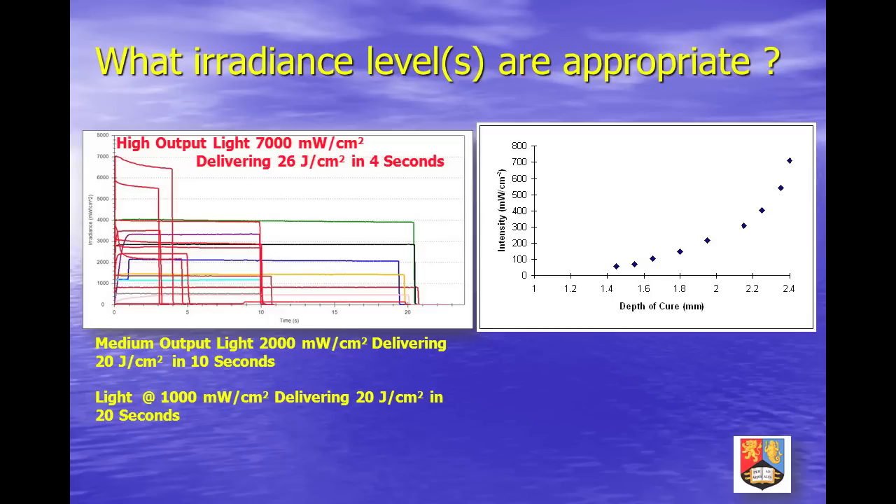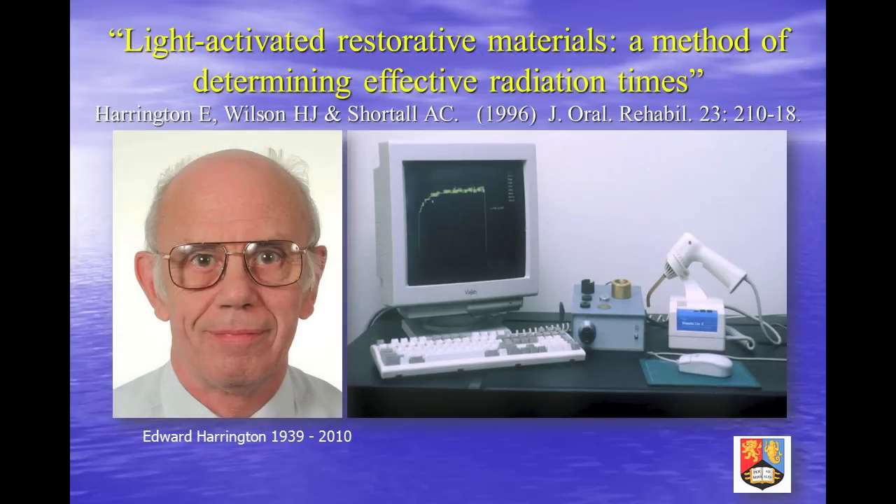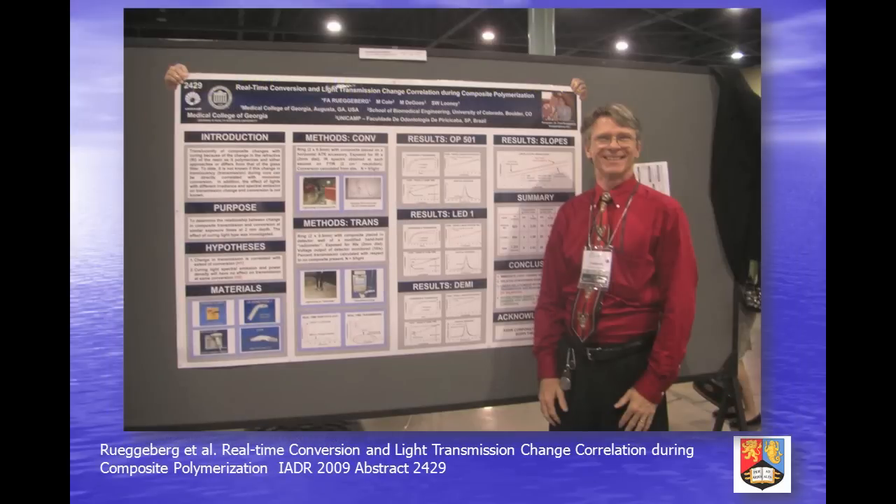My former colleague at Birmingham, Ted Harrington, developed a method of monitoring light transmission through a polymerizing sample as a way of predicting appropriate radiation times for any light source and material combination, using a simple PC-interfaced photodiode assembly. This idea has been furthered by the recent work of Professor Fred Rueggeberg, who has correlated light transmission changes during cure with real-time conversion. Hopefully, if commercially realized, such a method will make the decision over appropriate radiation times easier for dentists.